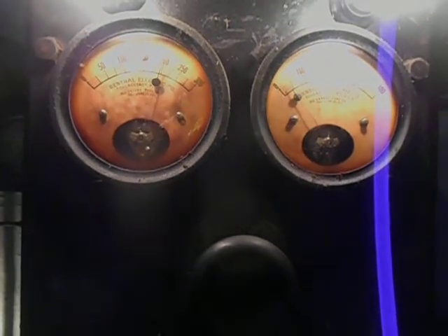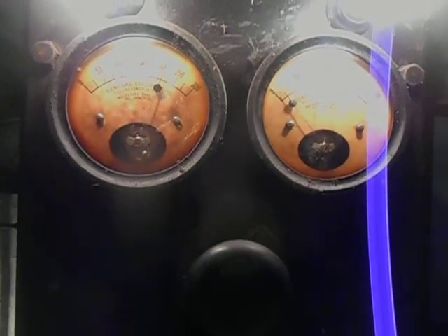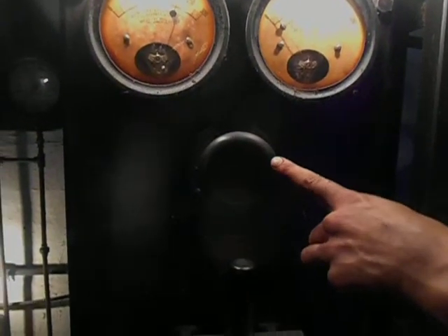It's decoupled. The motor is decoupled from the pump, so it's running loadless, which is why we're only drawing about 25 amps. When I cut it out and then cut it back in again, you'll see it draws a little more, of course, which is customary. The field rheostat for the DC generator is disconnected. We assume that's because the generator comes up to rated voltage when it's at rated RPM — I think they designed it to fix the field.